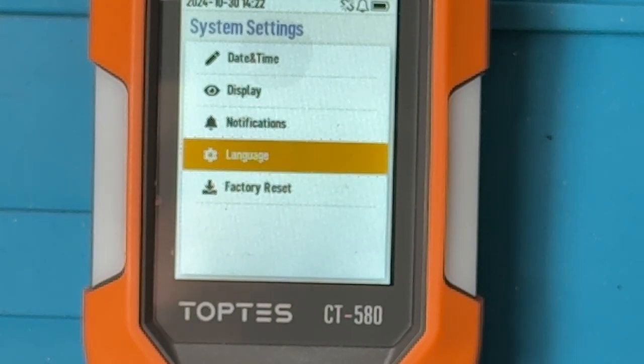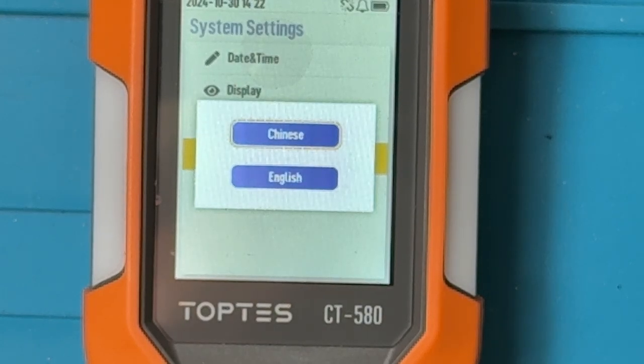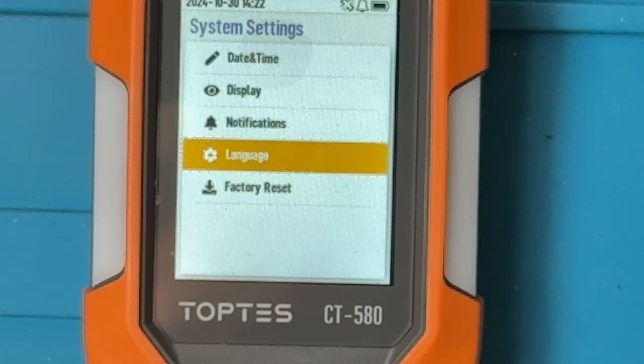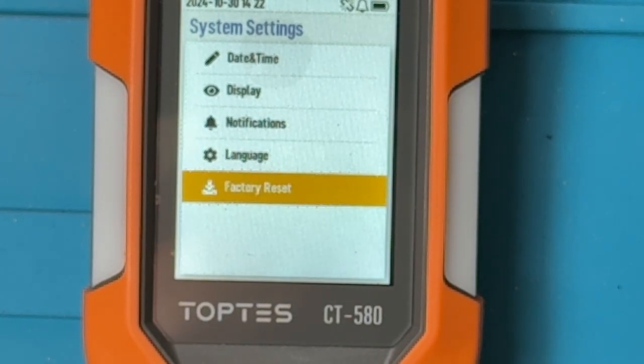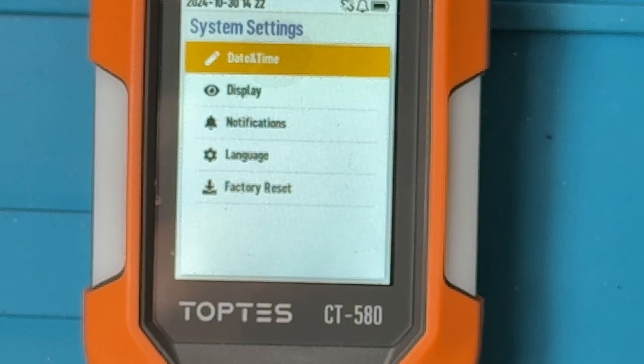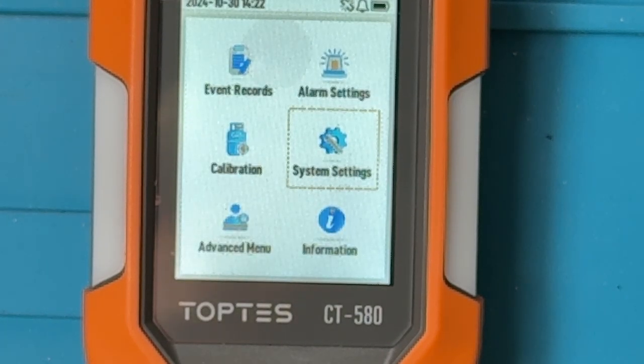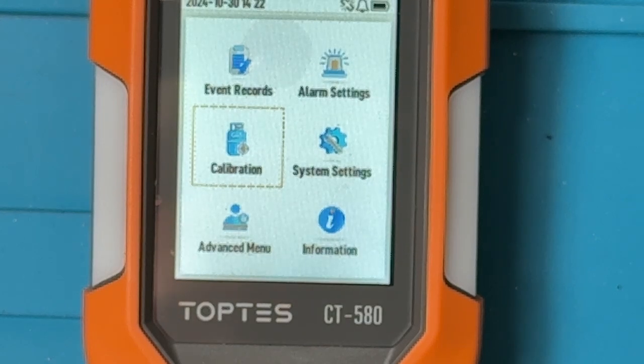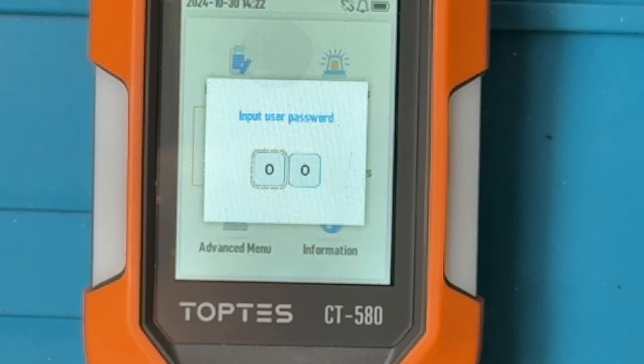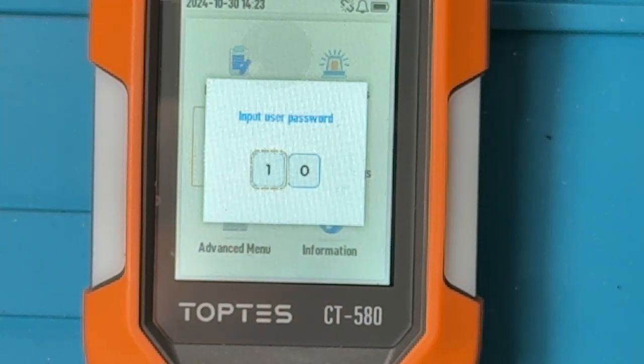Okay, language. So we can choose 2 languages, Chinese and English. We'll leave it alone. I like to be able to read what is being shown here. And then a factory reset setting, which I'm not going to make use of. Okay, press that power button or back button again. We see here calibration. The calibration requires a password to be entered in order to do a calibration, and the manual indicates what the default password is for the unit. And I'm not going to calibrate the unit because it's already been calibrated, but we can enter the default password. We can enter the password here.